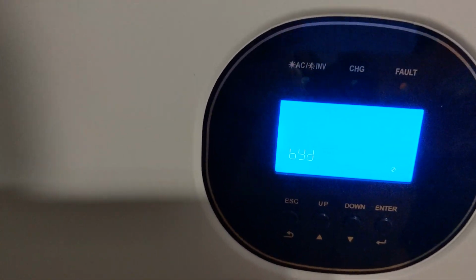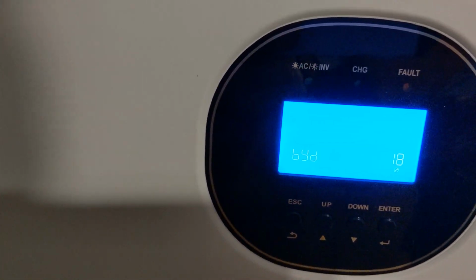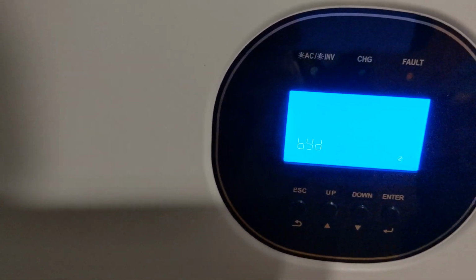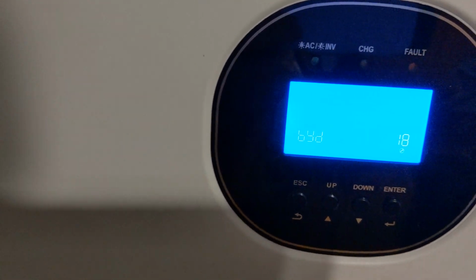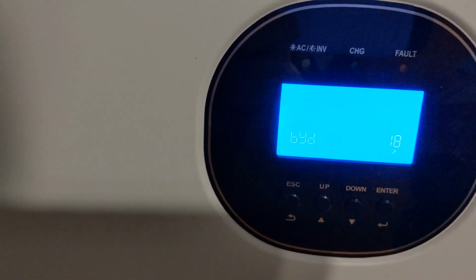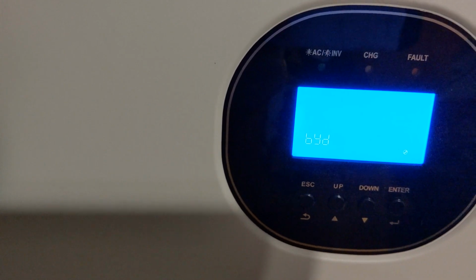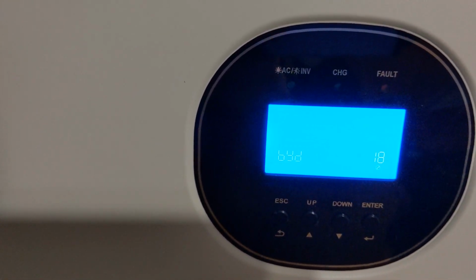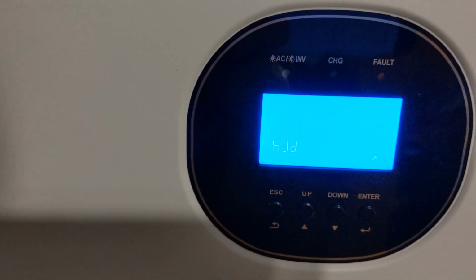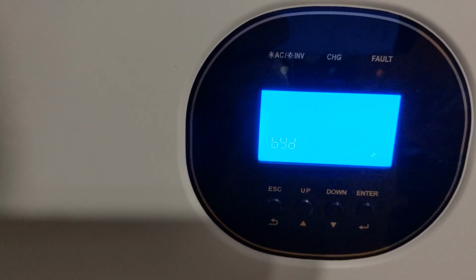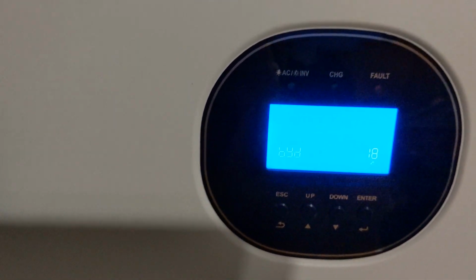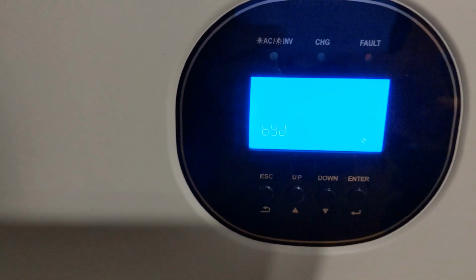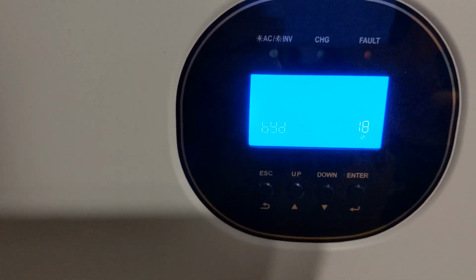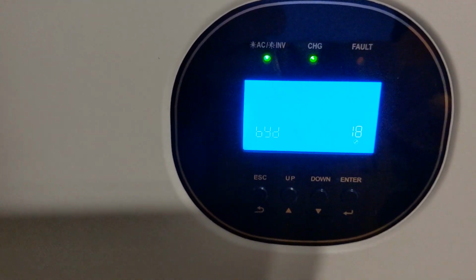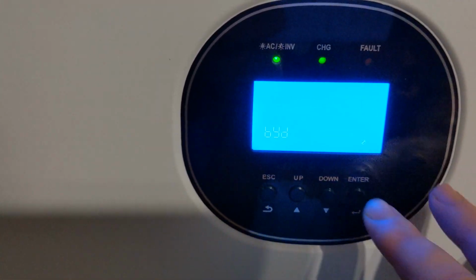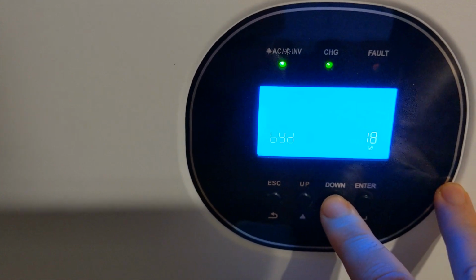This is the bypass disable, currently set to its default mode of disable versus enable, for the overload bypass. Basically, when enabled, the unit will transfer to line if an overload in the battery occurs. I don't have that enabled - my batteries can easily handle any load that's going to be on it, so I don't really have any use for that setting in my application.